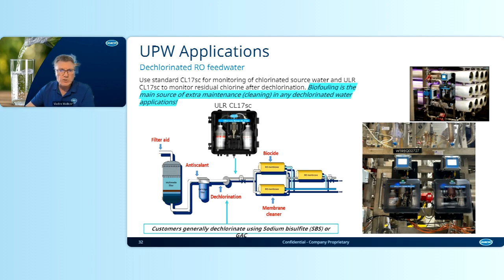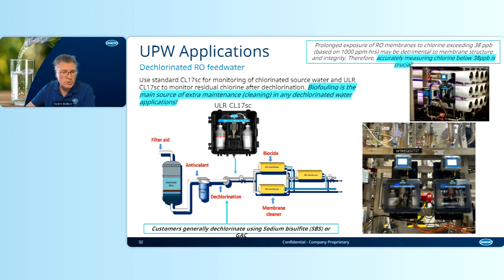Now, why the ULR version? Because prolonged exposure of RO membranes or nanofiltration membranes to chlorine exceeding 38 ppb may be very detrimental to their structure and integrity. Therefore, accurately measuring chlorine below that level, 38 ppb, is crucial, because treatment professionals need to maintain that very delicate balance between having some chlorine to keep uncontrolled biofouling growth at bay, and having it low enough to not damage the membranes.